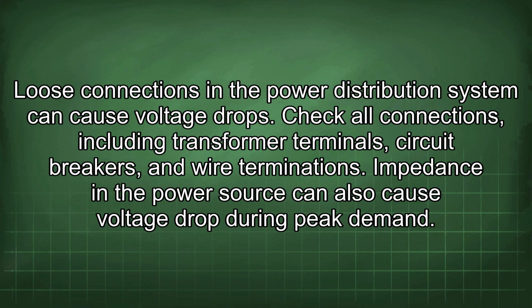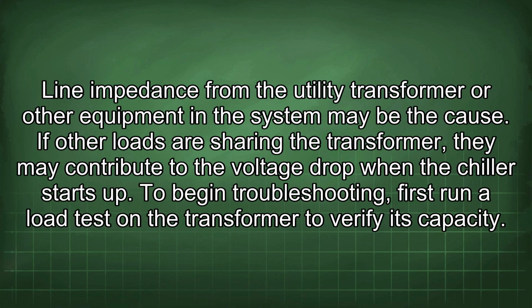Loose connections in a power distribution system can cause voltage drops. Check all connections, including transformer terminals, circuit breakers, and wire terminations. Impedance in the power source can also cause voltage drop during peak demand. Line impedance from the utility transformer or other equipment in the system may be the cause. If other loads are sharing the transformer, they may contribute to the voltage drop when the chiller starts up.